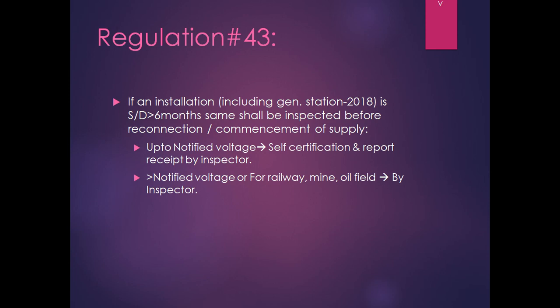Now, who will do the inspection? Below the notified voltage, self certification is sufficient. The report has to be submitted to the inspector. If the voltage level is more than the notified voltage, or if it is a railway line or mine or oil field, then the inspection has to be done by the inspector only.